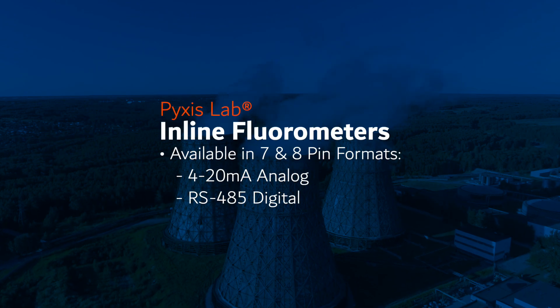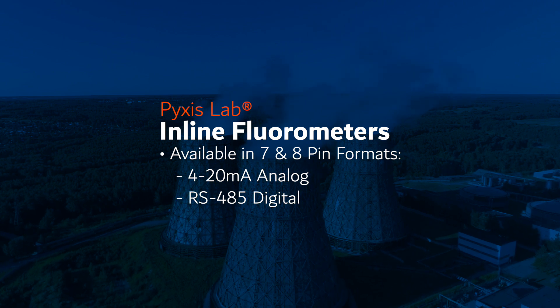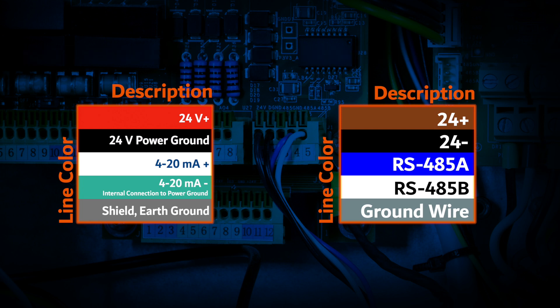All Pyxis standard inline sensors are offered in both 7-pin and 8-pin formats, providing users with a combination of 4-20mA analog and RS-485 digital outputs. This unique Pyxis capability integrates all necessary communication hardware within the sensor itself, allowing for connection to any conventional microprocessor controller, PLC, or distributed control system network.